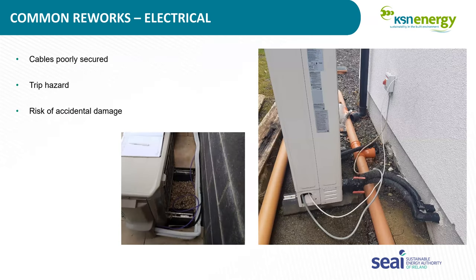Next thing from an electrical side, the picture, I probably don't need to describe it much. It's messy, it's there. I've small kids, the footballs and sliotars knocking it around the back garden. I know those cables wouldn't last long in my home, and that would be a thing that an inspector would come across, and he would ask that the contractor return and tidy up the cables and secure the cables and remove them. They're a trip hazard, you could get a live electric cable if it snaps out of it, probably fuse protection, but that would be something that an inspector would highlight at the time of inspection if they've seen it.